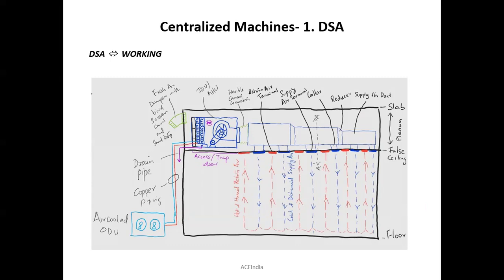First of all, the ductable split air conditioner, which symbolically means a ceiling suspended unit, isn't it? It is a ceiling suspended unit. So the connections are still the same as for the concealed AC itself. That means you'll have threaded rod connections with double nuts and locking washers. And typically on the true ceiling, you should drill some anchor fasteners. And these threaded rods are connected along with the anchor fasteners and then to the box body of the machine, that means the indoor unit, isn't it?